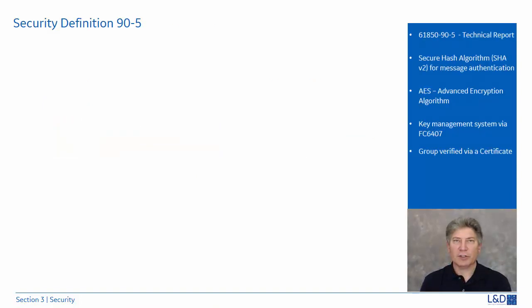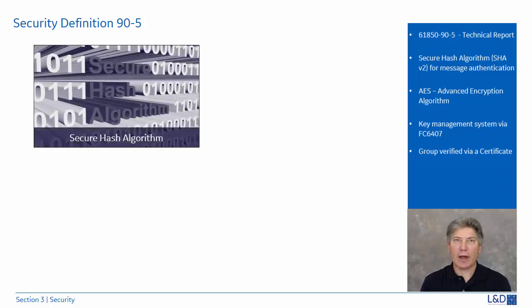The technical report 61850-90-5 defines how the routable GOOSE must be secured with a wide area network. First, it defines a secure hash algorithm. It uses an SHA-2, known as Secure Hash Algorithm Version 2, hash code, which is used for message authentication and integrity, similar to a CRC that places a tamper detection on the message.